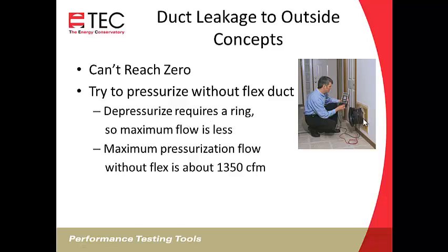If you've got a low back pressure across that opening, without the flex, you'll be able to get up to about 1350 CFM of flow. So you should be able to reach zero at that point, or you've really got leaky ducts or disconnected ducts, or you've got some major issues.